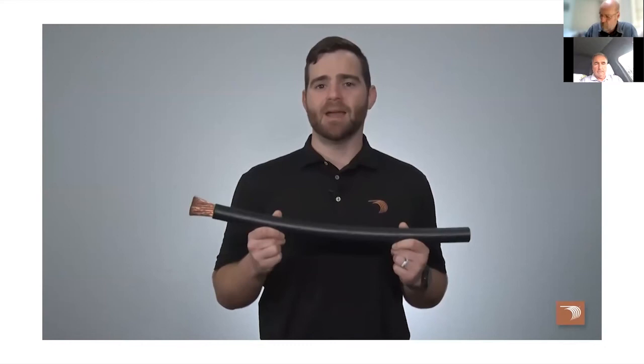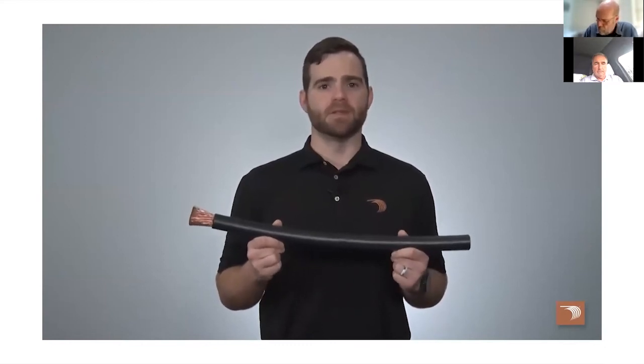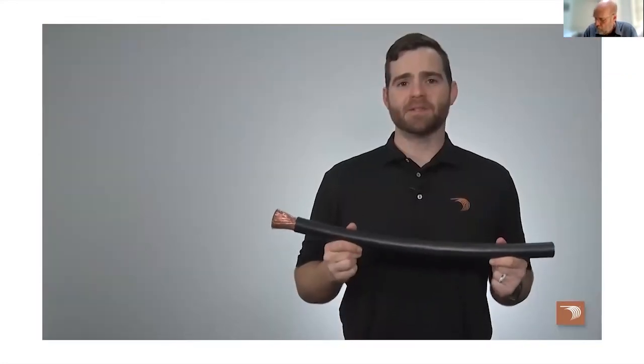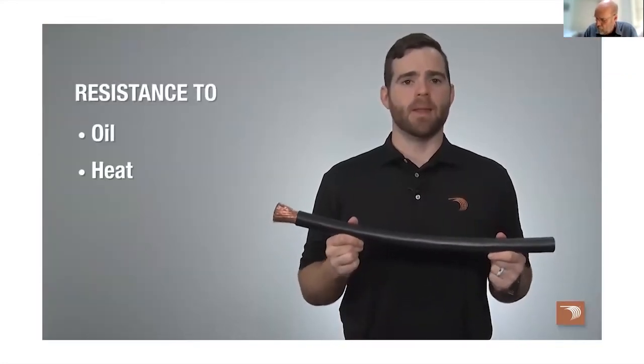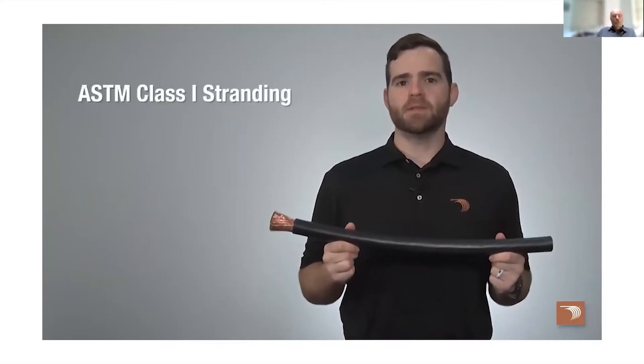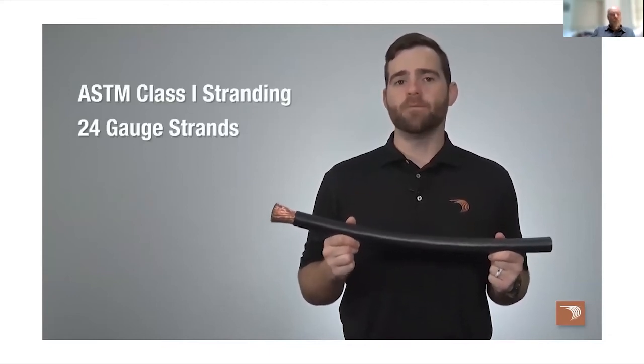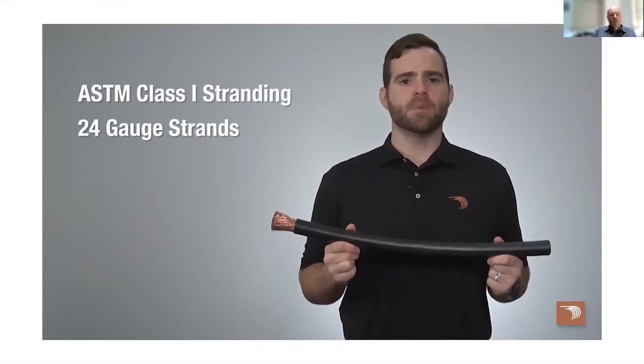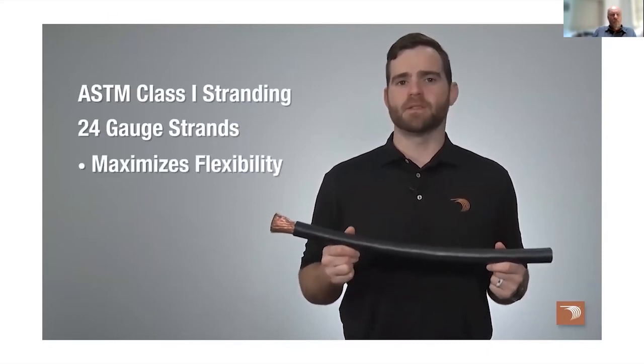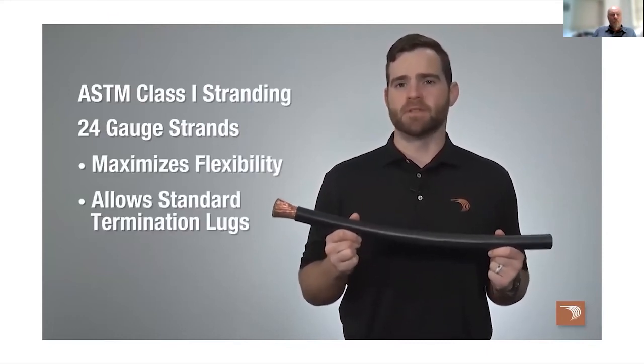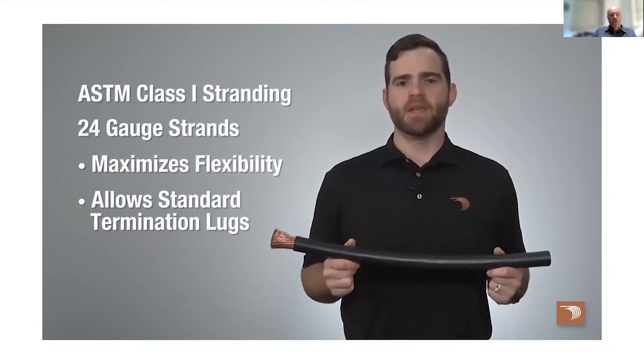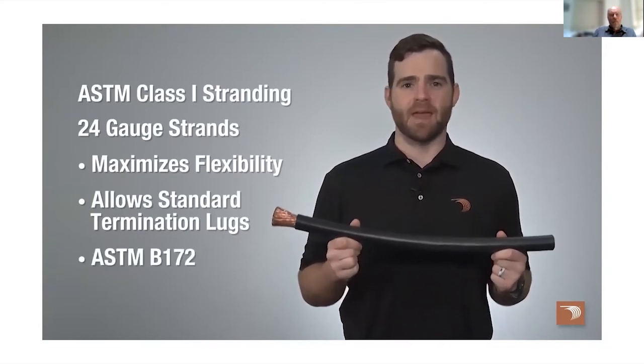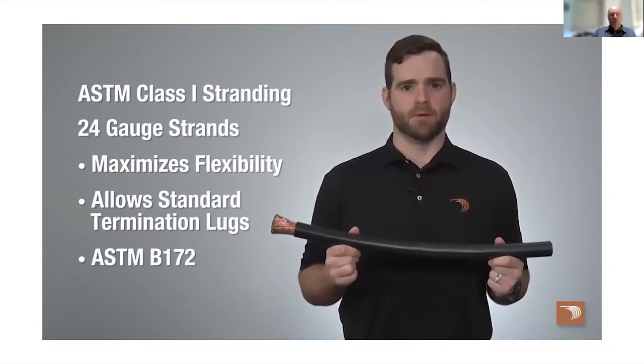THW-2/MTW insulation. It has a high strand count, which provides an increase in the conductive surface area and the flexibility. FlexCore has an excellent resistance to oil, heat, and moisture. It utilizes ASTM Class I stranding and 24 gauge strands. ASTM Class I stranding maximizes flexibility while still allowing the use of standard termination lugs. The standard conductors are manufactured under the ASTM B172 standard.